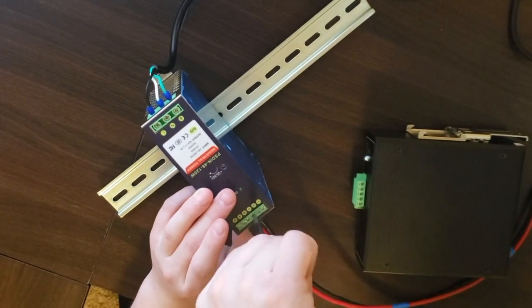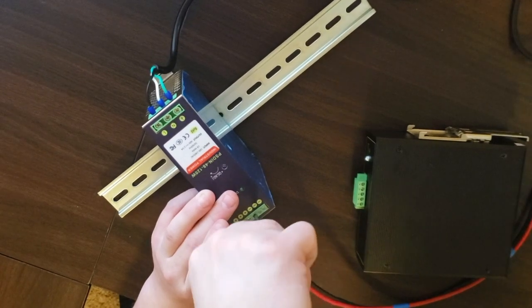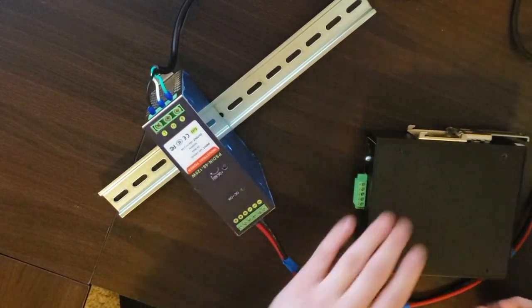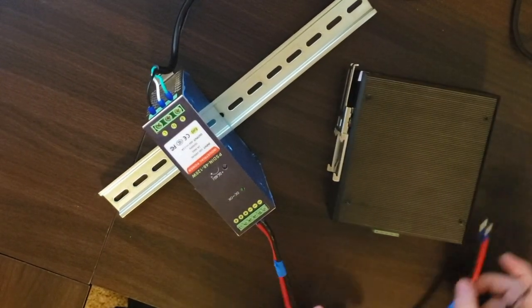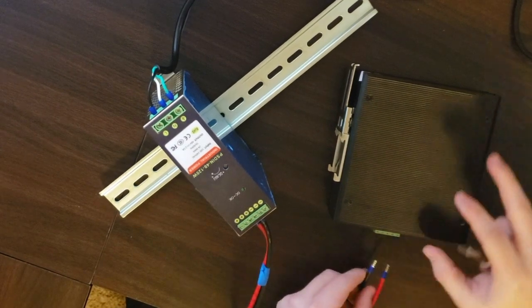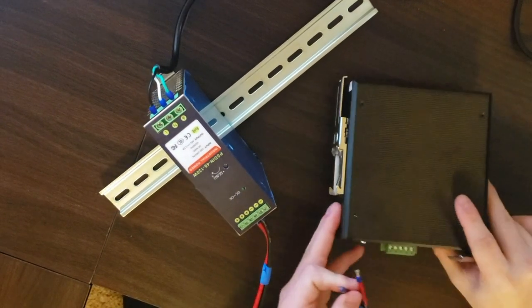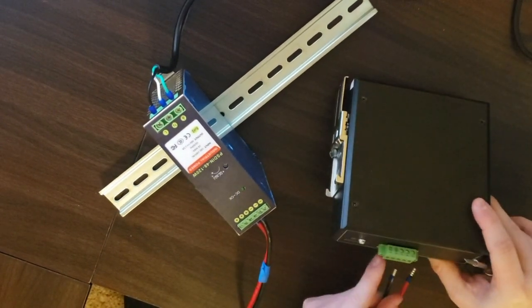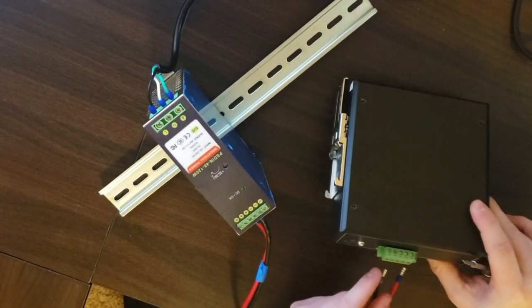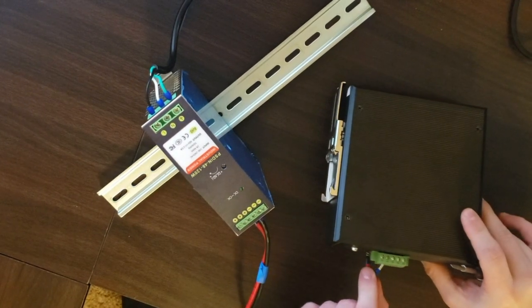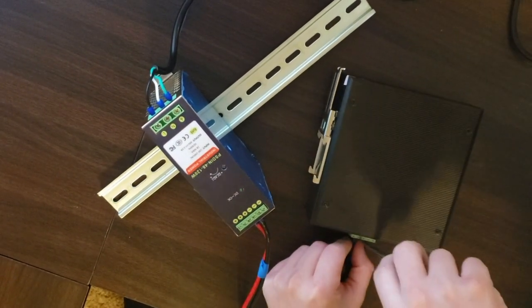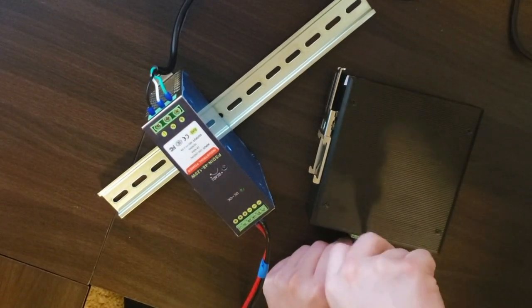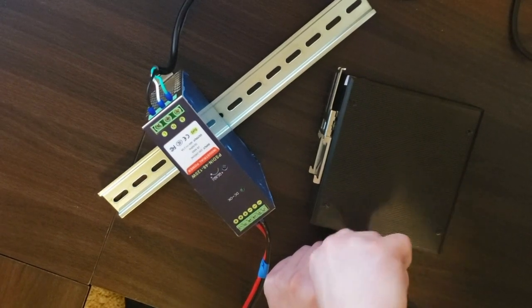The DC and OK connections at the top of the unit are a dry contact relay which is closed when the DC output is normal and open when the DC output is faulty. The contact rating is 1 amp at 30 volts DC or 0.5 amps at 125 VAC. This can help trigger an alarm if the DC output fails.